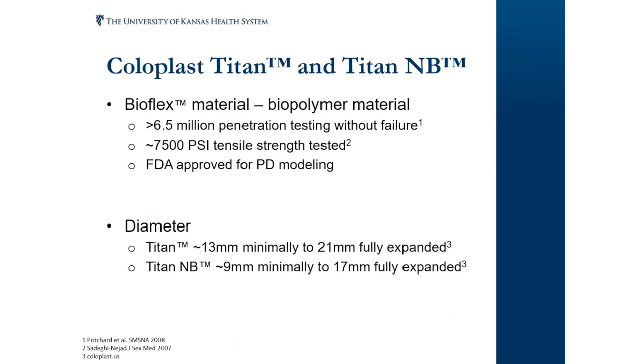Starting first with the Coloplast device, they have a BioFlex, which is a fancy name for one of their biopolymers that's compatible with human tissue. It doesn't cause reactions. A lot of this data comes from ex vivo studies. They've run tons and tons of different simulations and show that they can have greater than 6.5 million penetration tests without failure. Clinically, we know this number is way less than this, but this is, again, ex vivo studies. It could withstand up to 7,500 PSI. Later, I'm going to be talking about how much pressure we fill the devices with. A fully filled device is about 20 PSI. This tensile strength is important because while the device may have 20 PSI inside of it, as soon as you apply a pressure to it, say something like penetration, that pressure is going to go way higher than what you've pumped into it.